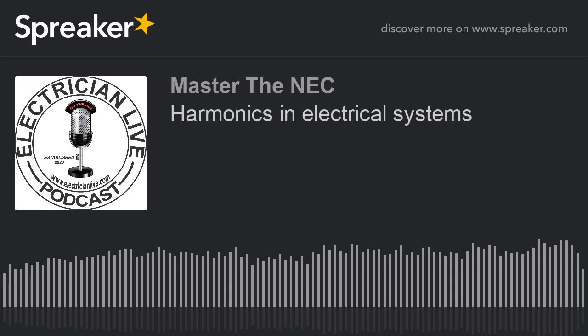So obviously I've got harmonic distortion. When I'm doing this, I'm thinking, well, my neutral better be able to handle this situation, because I've got this harmonic distortion, and it's going to play havoc on some of the equipment that might be on the system. But at least it tells me that I have harmonic distortion present in this condition in this building.